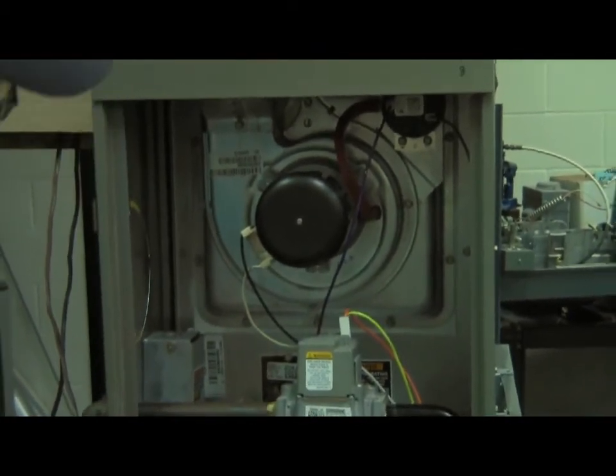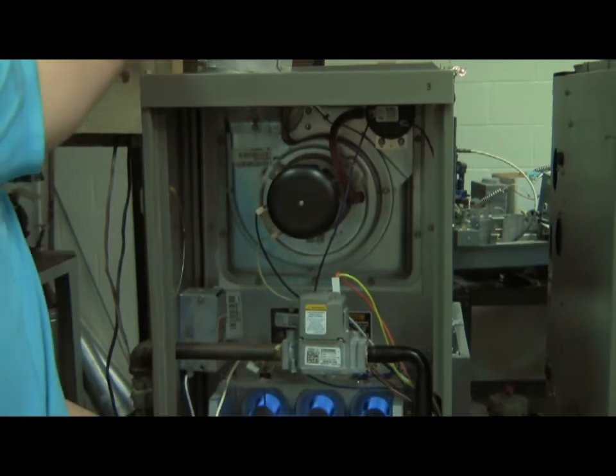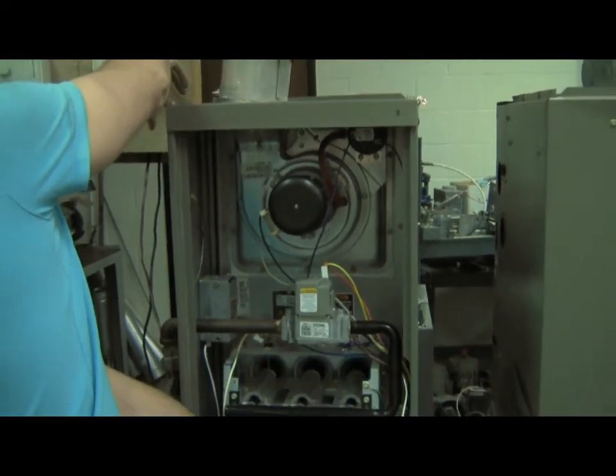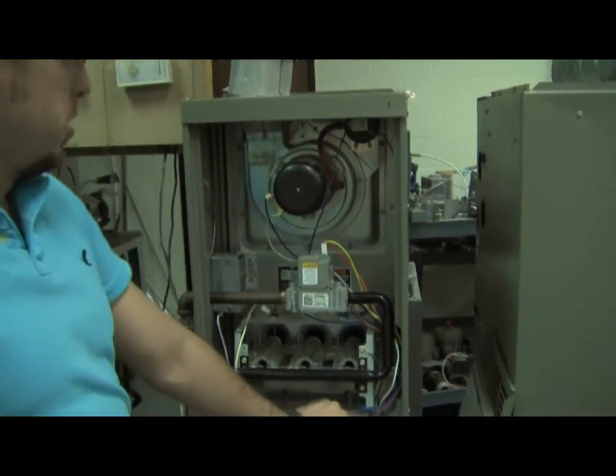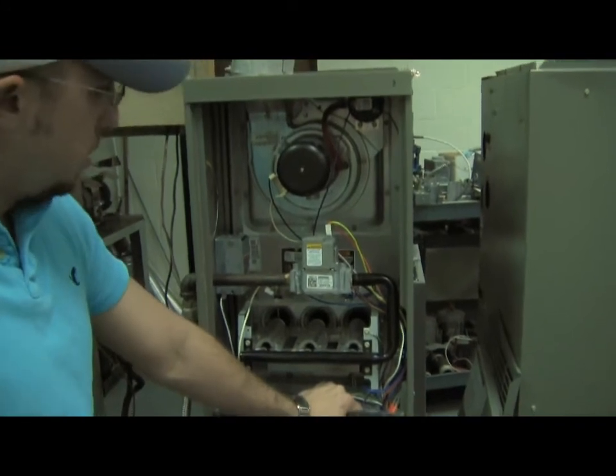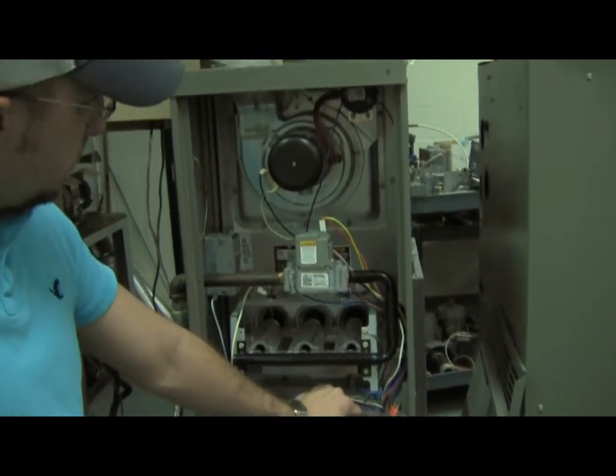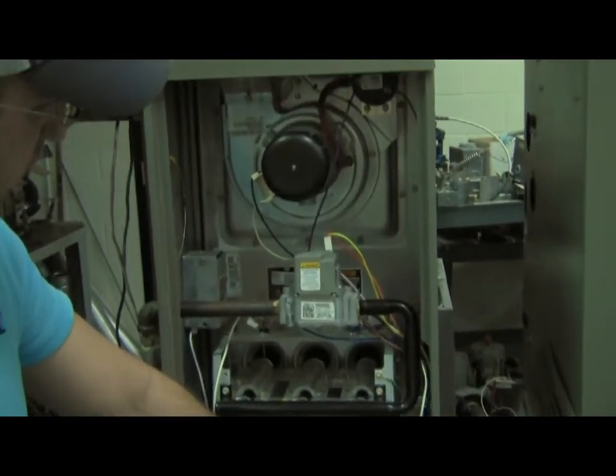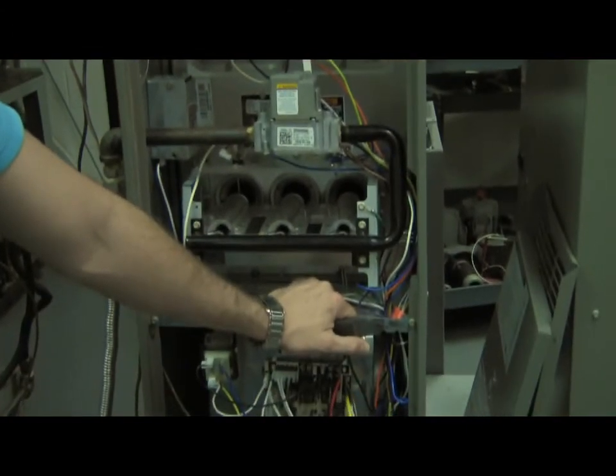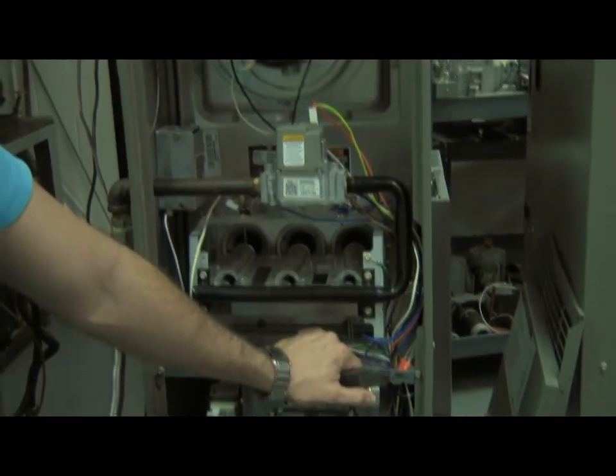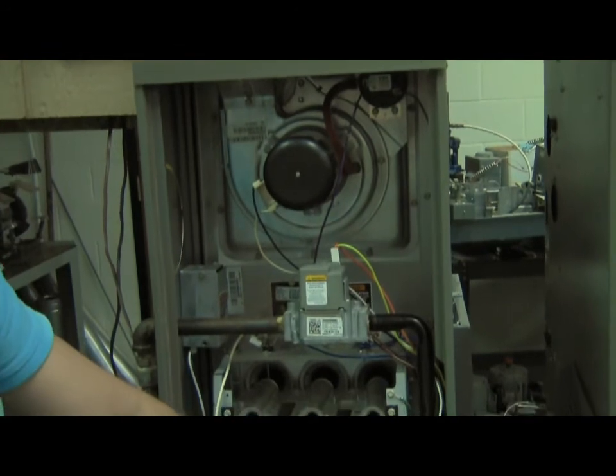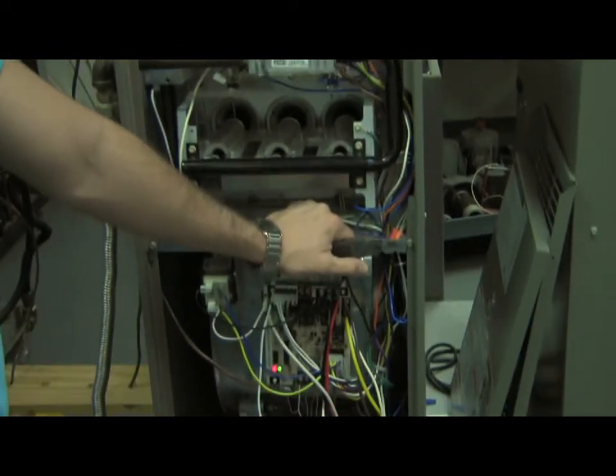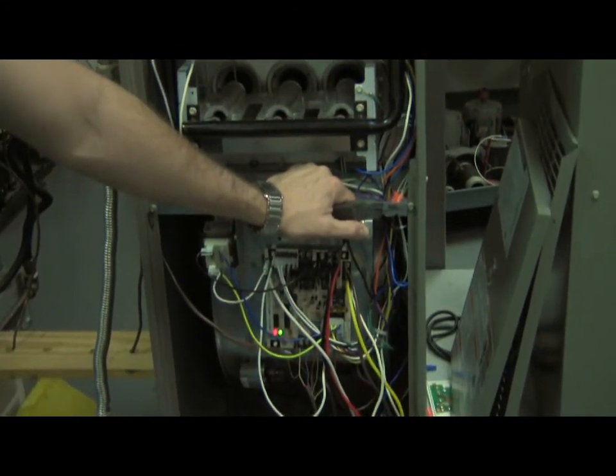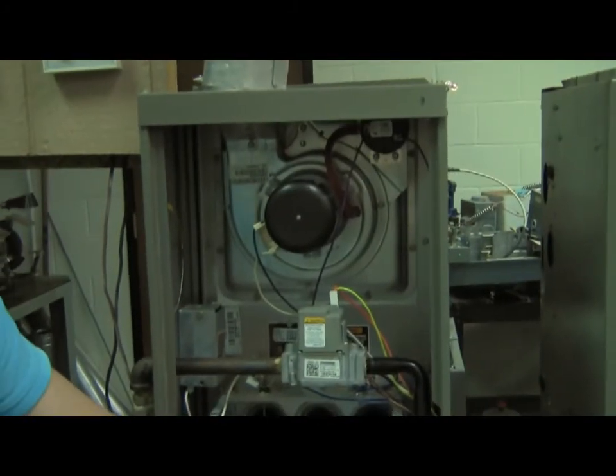And then, as soon as it reaches temperature, your flame will shut off, your induced draft motor and your blower will keep running. Your induced draft motor will shut off, and then your blower will shut off after its time delay is finished.